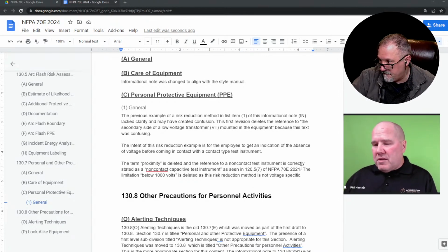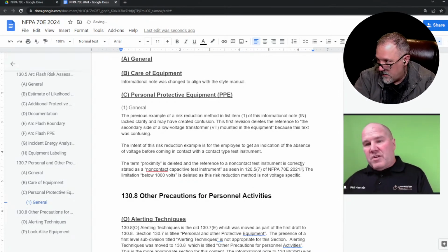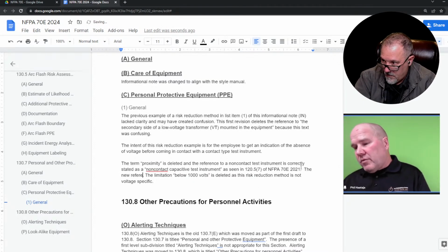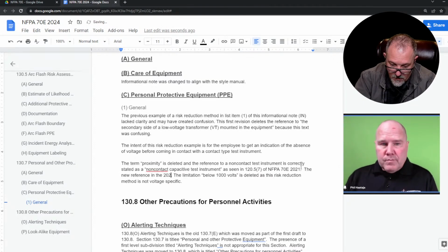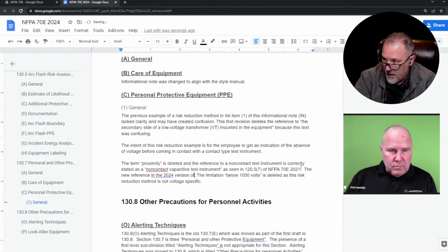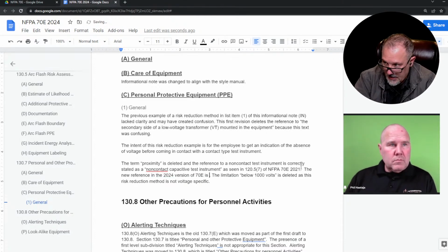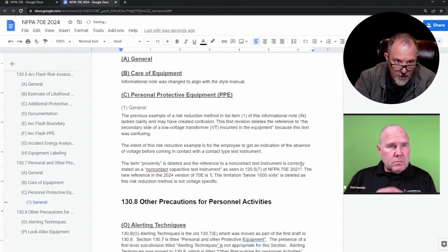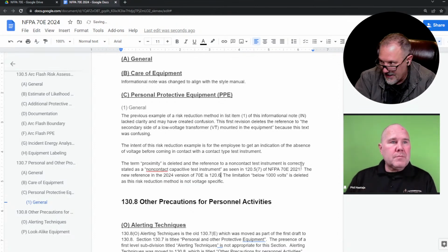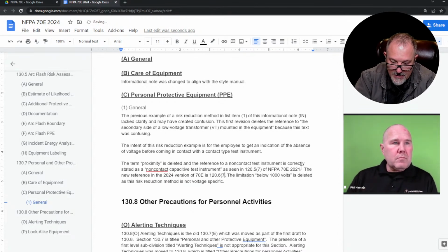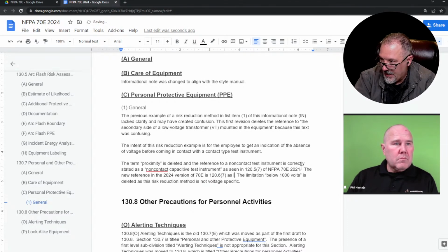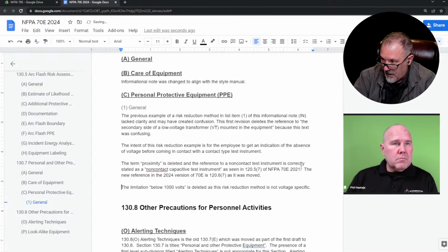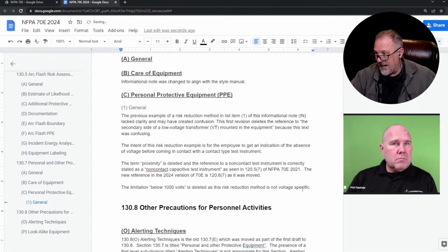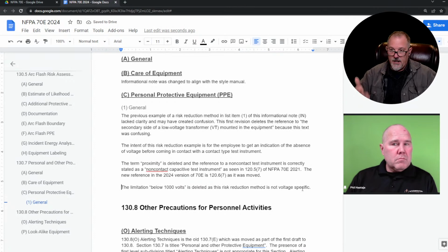120.6. Oh that's right, yeah. Because there is no 120.6 in the 2021 version. In the 2024 version of 70E, it's 120.6 paren 7, as it was moved. And the limitation below 1,000 volts was deleted, since this risk reduction method isn't voltage specific.